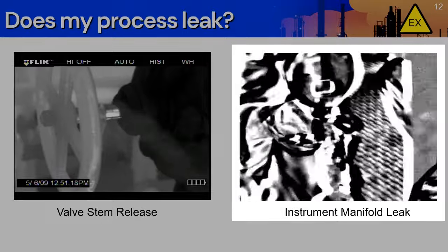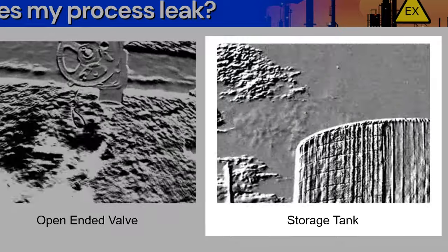Here we see a leak from an improperly installed needle valve. The leak remained undiscovered from the time the plant was first commissioned. Here we see a sample valve that was not fully closed after a sample was taken.